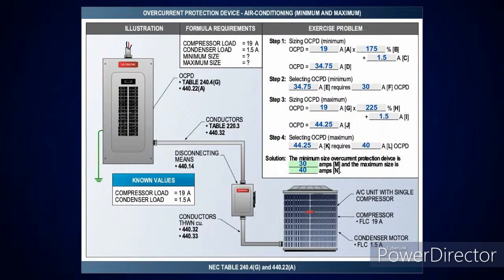I said, when UL looks at this, not only do they have to look at the UL standards or any other standards, they also look at the NEC. And I said, you can take the amperage that's on here, put that percentage on it, and then add your compressor or your condenser motor to it, and I guarantee you're going to get the same size. That's how they make these decisions. They do things in compliance with the National Electrical Code to get that listing and labeling.